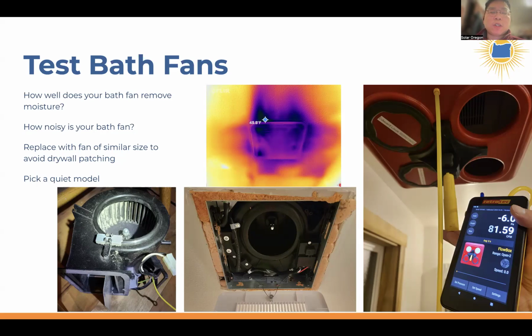And then afterwards, air seal that bath fan so that you're not having a thermal image like the one in the middle of the slide, which shows that during a blower test, the bath fan was not air sealed, and so it was leaking a ton of cold air into the conditioned space. And when it comes to bathrooms, it's not just air leakage. The moisture in the bathroom is also going into the attic and damaging the insulation up there.